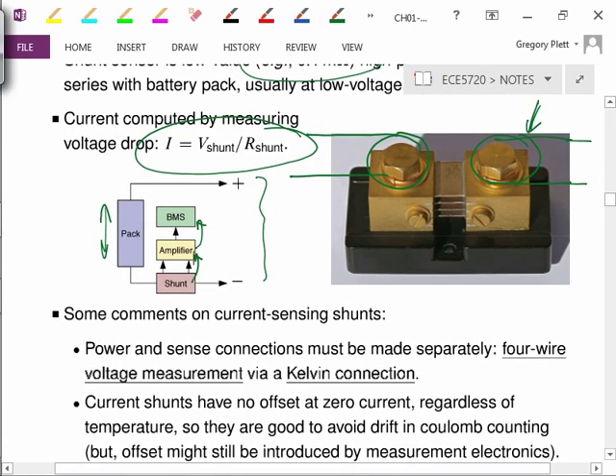You'll notice on the shunt resistor that there are 4 screws, or bolts, rather than 2. The minimum requirement would be 2 because I need to put power through this shunt somehow, but I also need to connect a voltage measurement to it. If I were to connect some voltage measurement lead right there and right there, there's a large resistance between that lead and the calibrated part of the resistor. The calibrated part really is from here to here, and all of the connection resistance can actually be much higher than the 0.1 milliohms of the calibrated part.